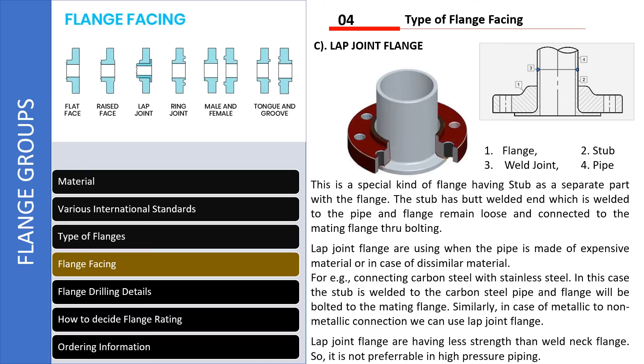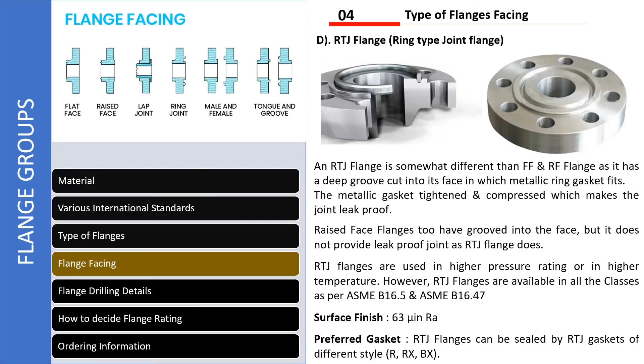Ring type joint will be having a different type of facing. If you see, there will be a ring type facing on the flange. This kind of arrangement is there only when we are going ahead with very high pressure services, high pound rating. B16.5 and B16.47 clearly define the requirement or the design for ring type joint flanges. So the ring type arrangement will be there, which will be available for ring type gaskets also. So an RTJ flange will be having this kind of surface with RTJ gaskets in between. These are only used for very high pressure services where raised face type of facing may get leaked. So these are very much leak proof types of joints for very high pressure ratings.